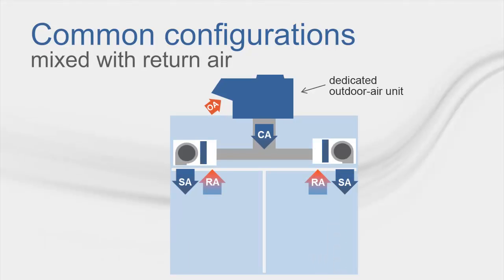Another common configuration is to design the DOA so that the conditioned outdoor air is delivered to the return air intake for each of those room's fan coils. The fan coils then condition that mixed air to meet the remaining cooling and heating loads.